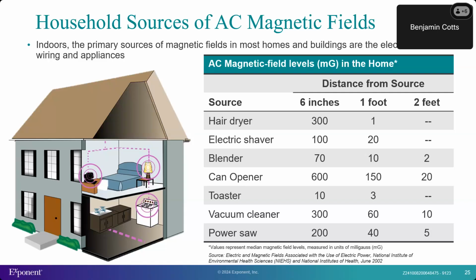For instance, if you look at a hair dryer, a typical usage distance might be about 6 inches, and at that distance the magnetic field strength is about 300 milligauss. Whereas at a foot away, it's dropped off to about 1 milligauss, and at 2 feet away it's basically below background levels. Another example might be a vacuum cleaner, which similarly has a magnetic field level 6 inches away of about 300 milligauss, but people don't typically use vacuums that close to themselves. They're going to be a foot or two away, at which distance the field levels have dropped to 60 or 10 milligauss, respectively.